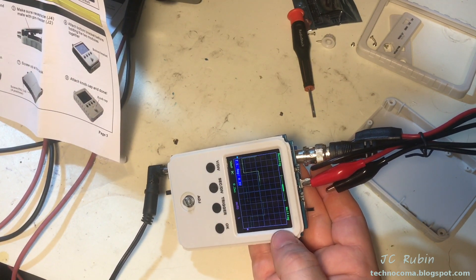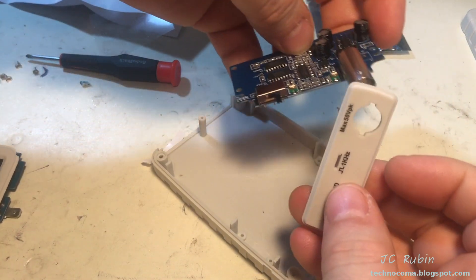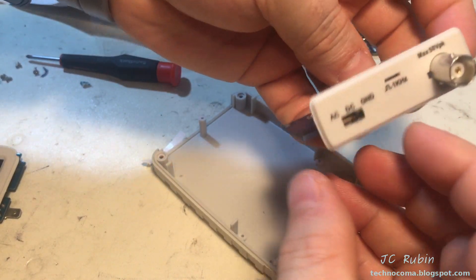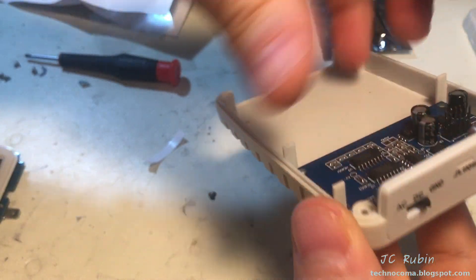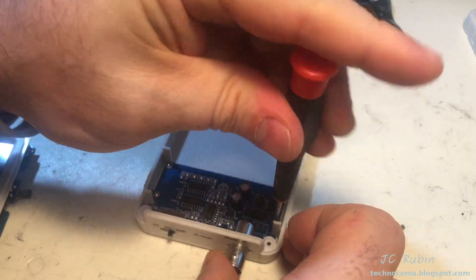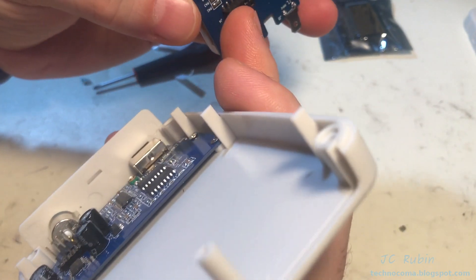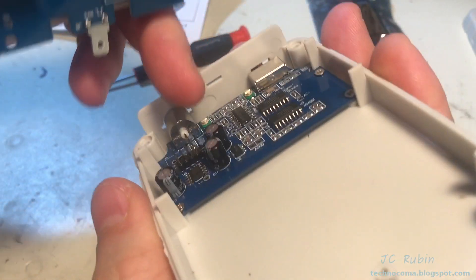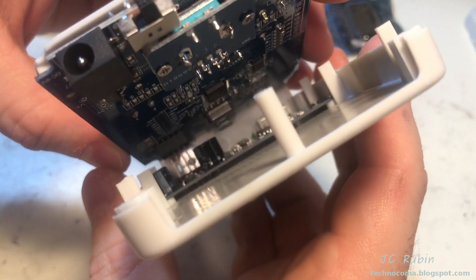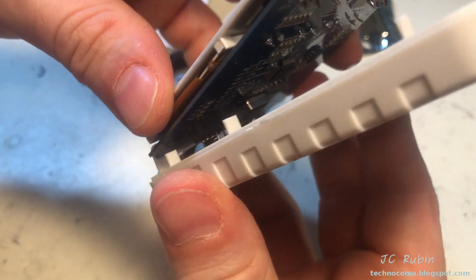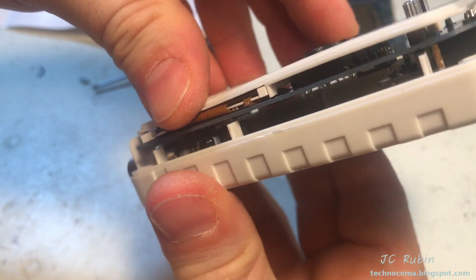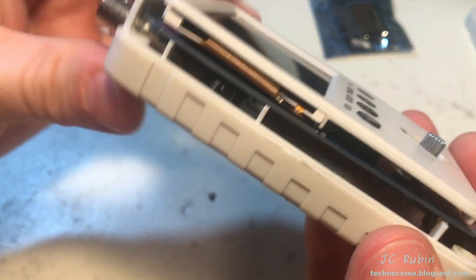Let's put everything together now. In this plastic case we assemble the analog board into the back cover. Now I'm going to slide this piece through like that. It goes into these grooves, it sits here and we're going to secure it with four screws. Now this test pin hanging off the end goes through this little slot while this connector down here and this connector over here connect to each other. I slide that in and then I bring this across here, line those pins up so I don't bend them, there we go. And then I just push this down like that. Everything's sitting in position, so it appears.